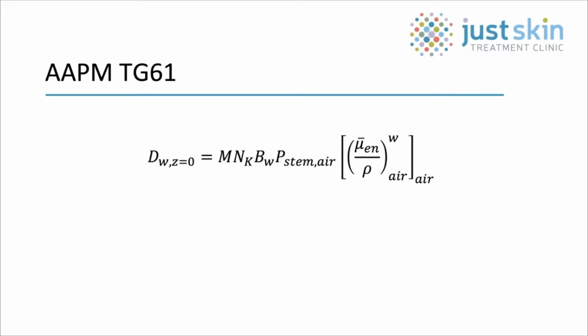BW is the backscatter factor taken from table 5 in TG61 from the IAEA website. Be sure to use the HVL obtained using 100 centimeters SCD or the appropriate distance. The stem can be assumed to be 1, which makes life easy. The new TRS-398 has tables of geometry factors, and if you look at the 10 and 20 kV energies for this ion chamber, you'll see the same result. The mass energy absorption coefficient ratio can be taken from table 4 in TG61 or from the IAEA website. In my case, I use the HVL values from 100 centimeters SCD.